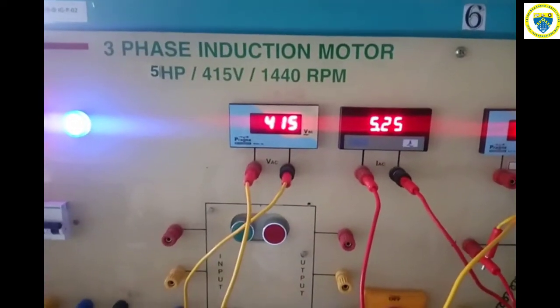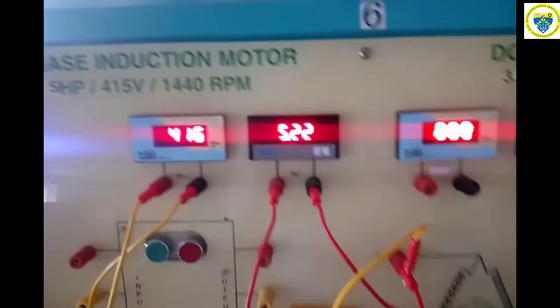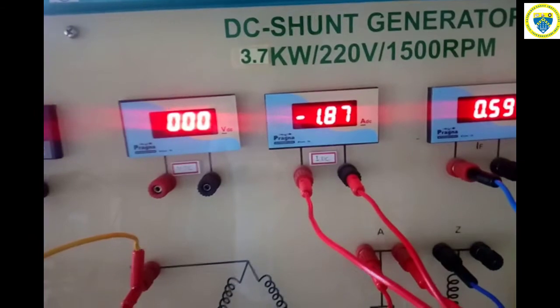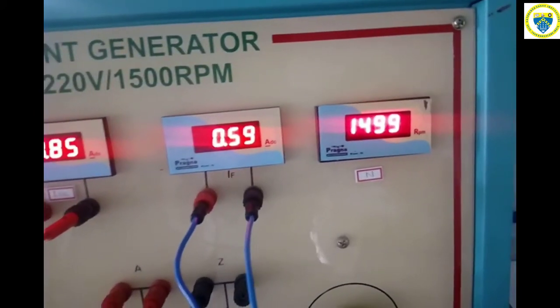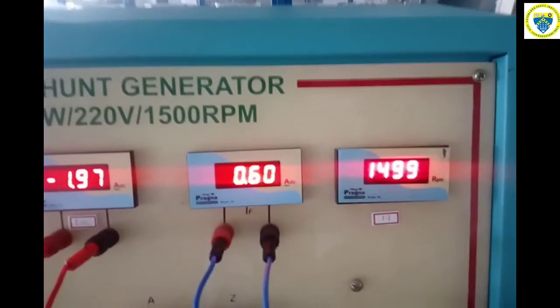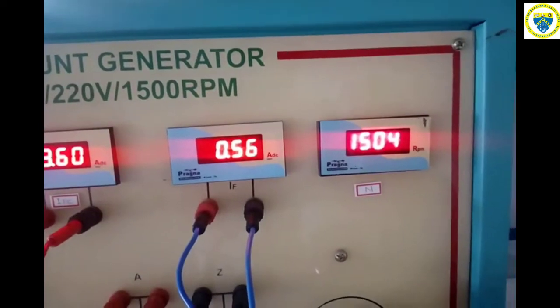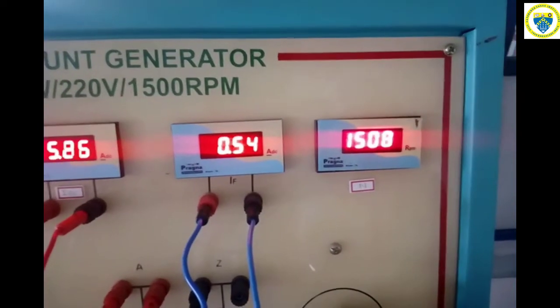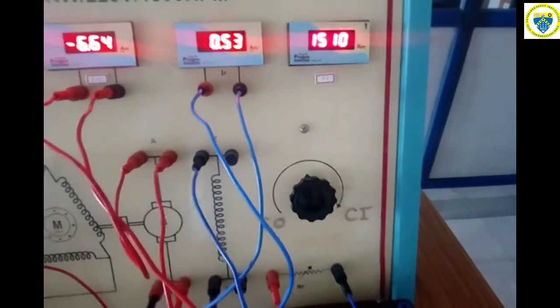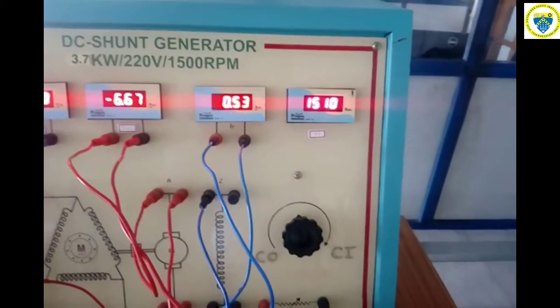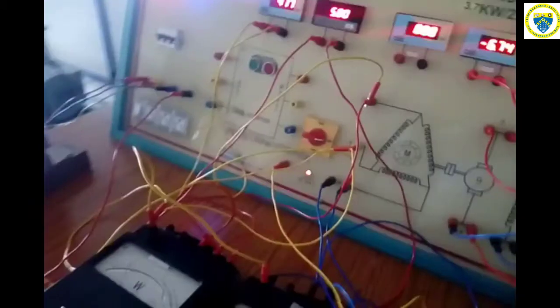So at each position of the rheostat, we can note down the input watts W1, W2, and also the input voltage given to the induction motor, generated voltage 415 volt, then the AC current, then the field current DC, then the RPM. So RPM can be increased slowly in steps of 3 to 4 RPM. So we have to load the induction generator in steps of 3 to 4 RPM, gradually varying the field rheostat. At each step, at each RPM, as we load the induction generator, all the readings are noted down.